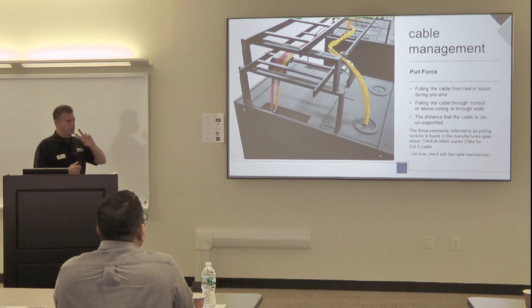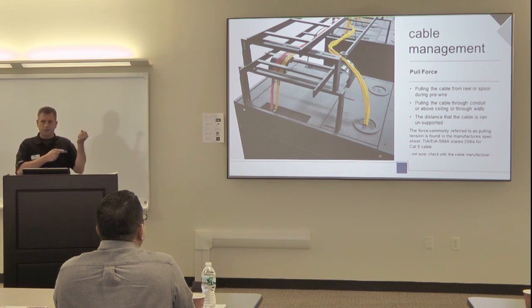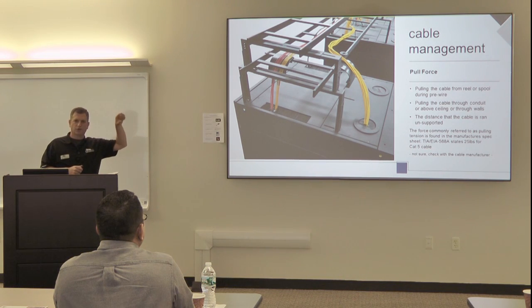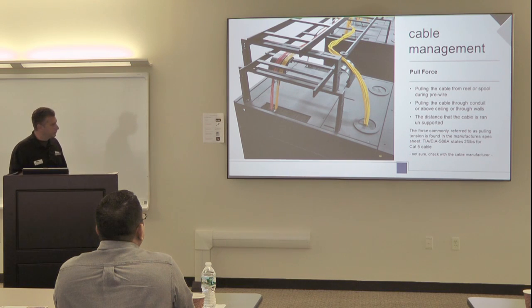Pull force can come in two different ways. There's the way of when you're doing pre-wire. If you pull on a cable, it's about 25 pounds of force. So you've got a bundle of cables. If you feel like you're really putting your weight into it, you should probably stop and check and see what's going on. Don't continue to do that. There's a lot of things that can happen to the cable by doing that.